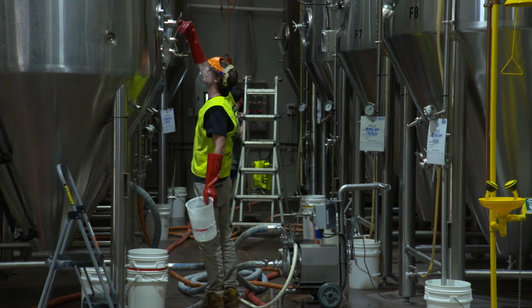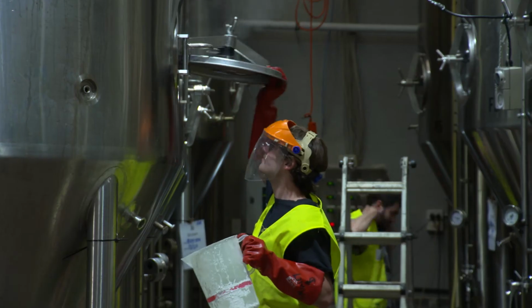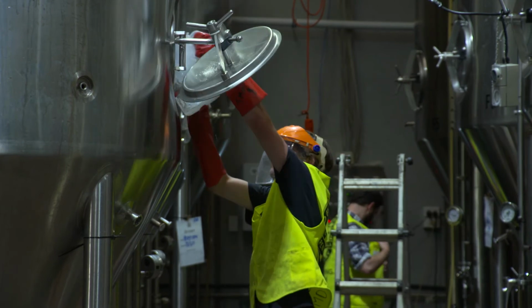Mornington were exceeding their supply capacity of about 80 amps a phase. And traditionally, in order to increase that, you would need to go and apply for a mains upgrade for the facility, and that can take anywhere between 6 to 18 months to actually get done. So most breweries would rely on a generator there, and a generator is like either a generator or mains solution. The generators very rarely run in parallel with mains, and particularly here for the brewery, that meant that they would be running generator for 24 hours a day, really until March or April when the seasons started to get cooler.